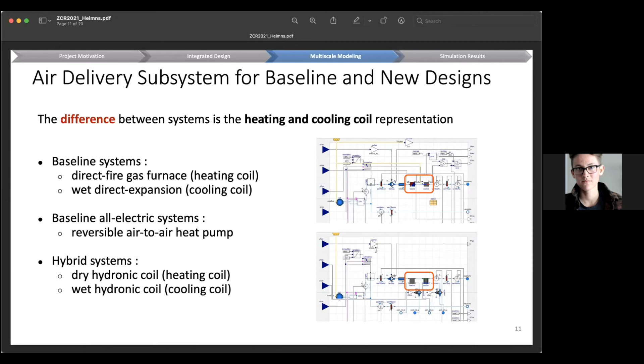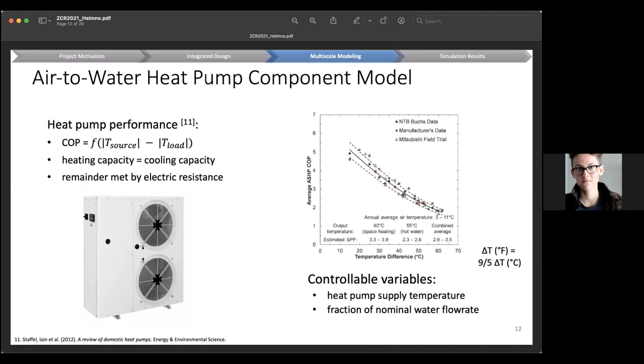The heat pump model is a simple COP model, and we're actually looking at field data. There were hundreds of heat pumps tested in the field, and their coefficient of performance, or COP, was determined as a function of the temperature difference—source side versus load side. These data were compiled, and this is what we're using to represent the performance of our heat pump in the model.